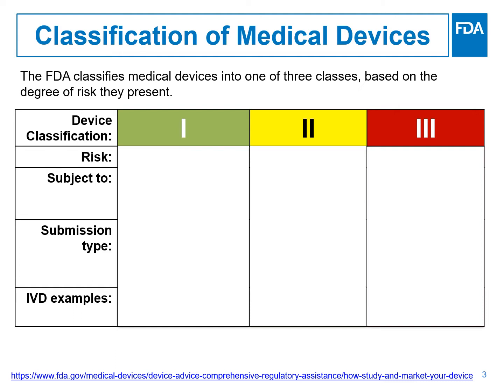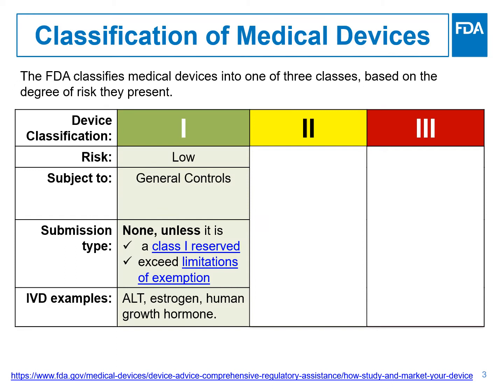Let's start with Class 1 devices. These are considered low risk and are subject to general controls, which are the basic authorities of the medical device amendments that provide the FDA with the means of regulating devices to ensure their safety and effectiveness. General controls include the provisions of the Act pertaining to things like adulteration, misbranding, device registration and listing, pre-market notification, and good manufacturing practices, among others. Most, but not all, Class 1 devices are exempted from the pre-market notification procedures.